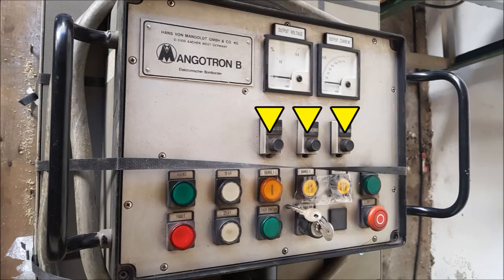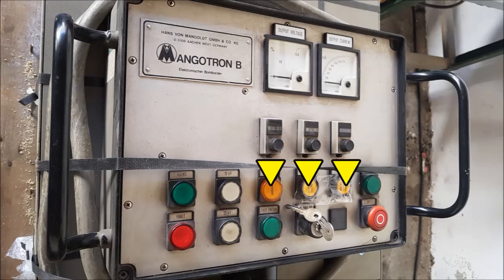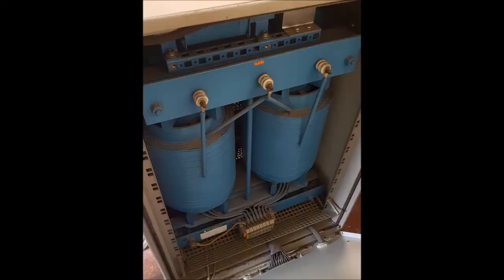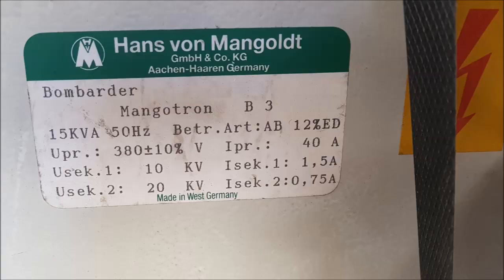It has 3 presets you can dial in here, and then you can just jump to each preset with these buttons. And the electronics will keep the tube current on that exact value by regulating the power to the transformer with a thyristor power controller. That's like a high power dimmer for the bombarding transformer. In the back of the cabinet we have the power transformer that connects to the tube. And here's the label saying that it can do either 10 kV at 1.5 amp or 20 kV at 0.75 amp. This output is lethal.